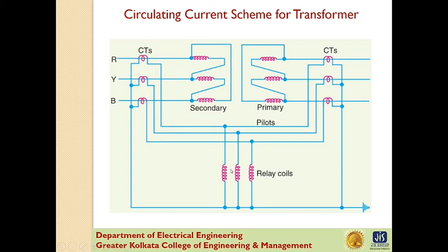Now, when there is a fault, the current on these CTs and the current on these CTs are not equal, and differential current is flowing through these relay coils and causes the circuit breaker to operate. And under normal operating condition, the currents in both CTs are the same, so no current is flowing through these relay coils and the circuit breaker is inoperative.